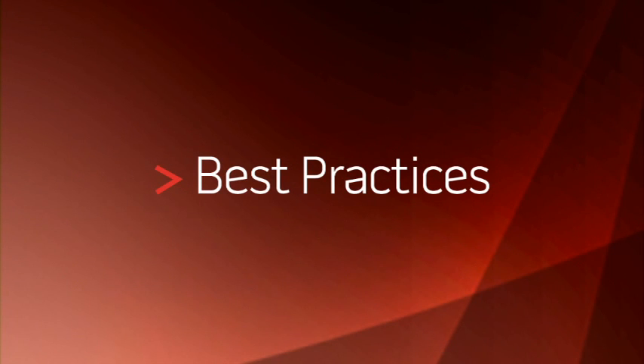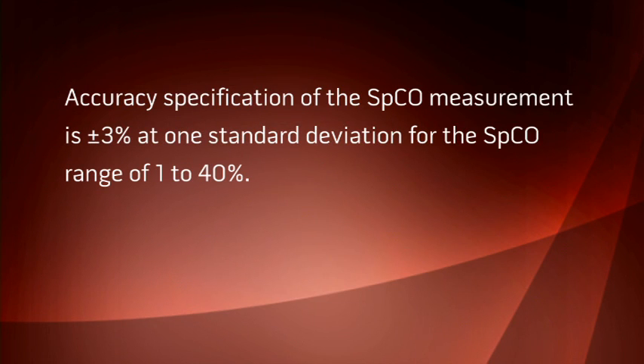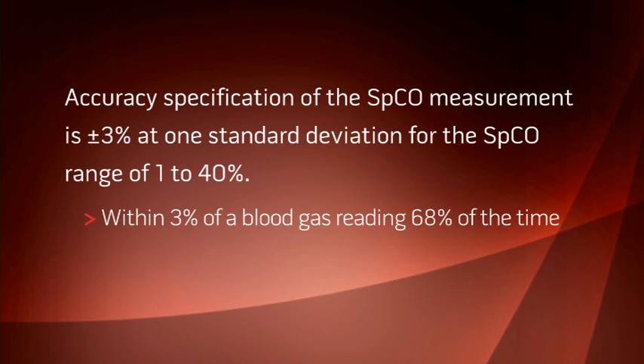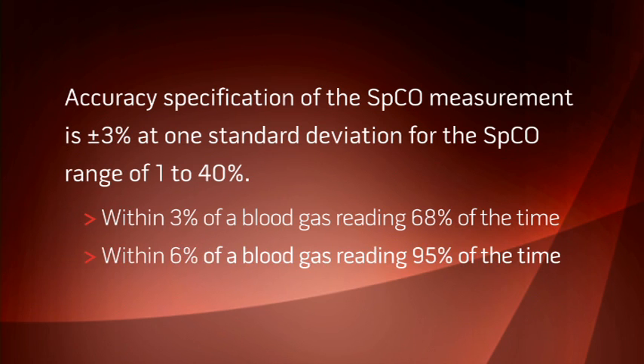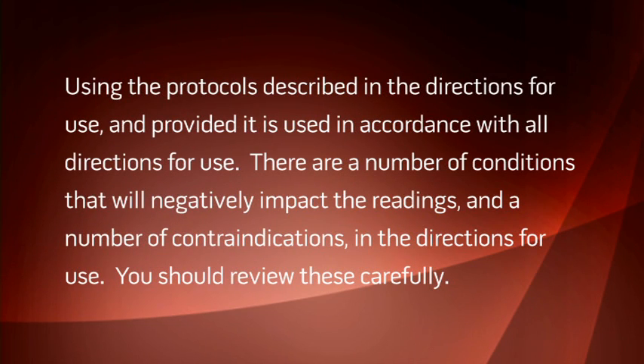Now that you're familiar with the operation of your device, there are several important tips and best practices to remember for successful SpCO monitoring. The accuracy specification of the SpCO measurement is plus or minus 3% at one standard deviation for the SpCO range of 1 to 40%. That means that the device will be within 3% of a blood gas reading 68% of the time, and within 6% of a blood gas reading 95% of the time, using the protocols described in the directions for use, and provided it is used in accordance with all directions for use.